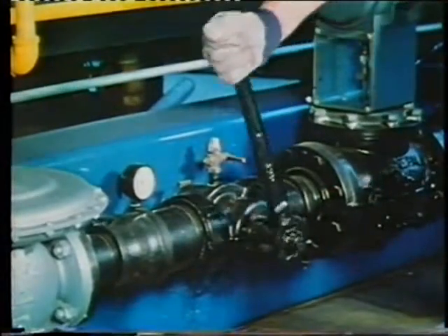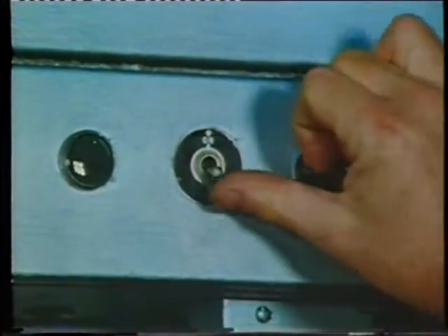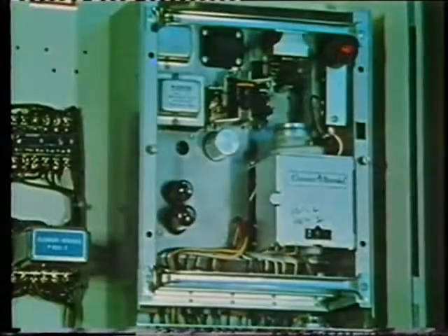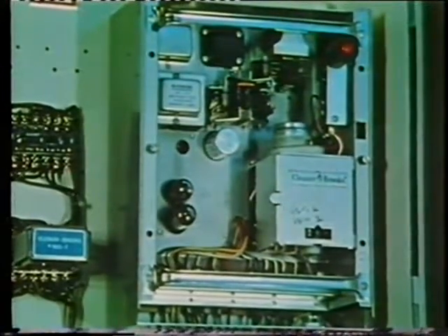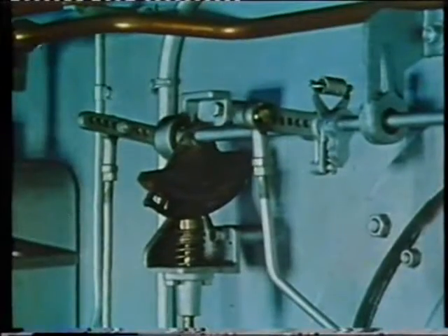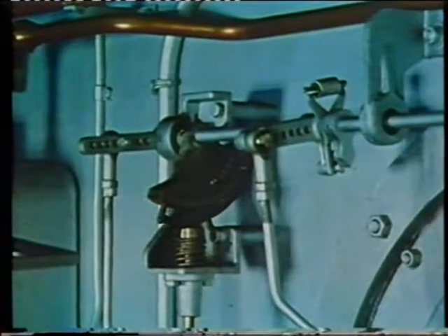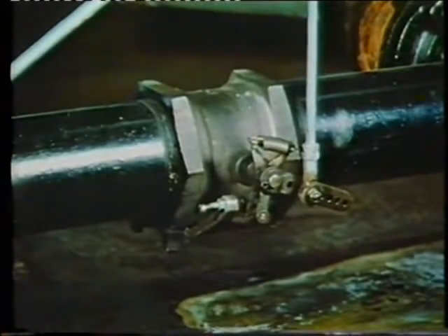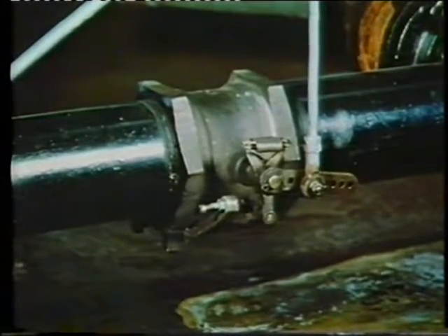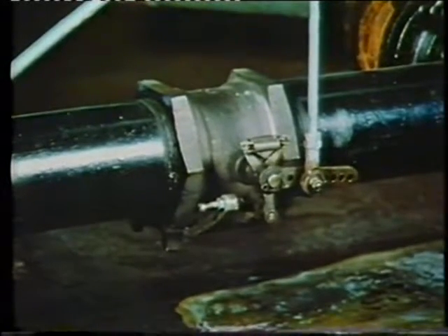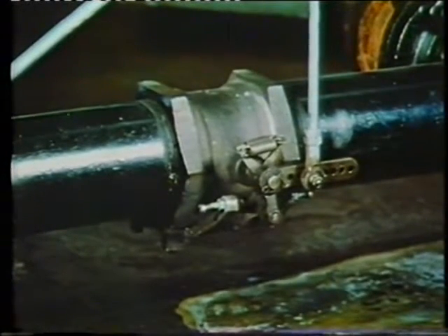The main gas valve is opened. The control switch is flipped on, and the programmer initiates the ignition sequence as it did for burning oil. The modulating cam moves the draft lever and the butterfly valve disc as the programmer calls for changes in the air-gas ratio to meet load demand. The same modulating motor operates the cam for both fuels.